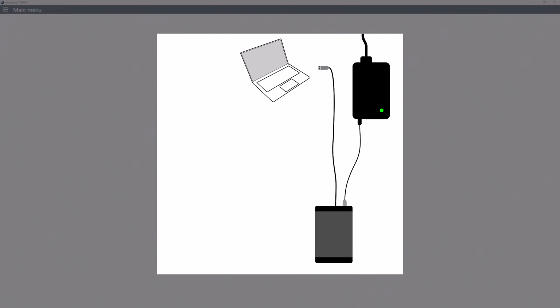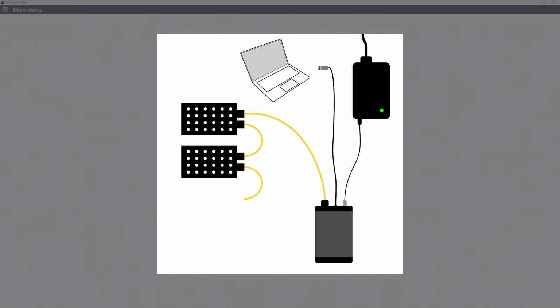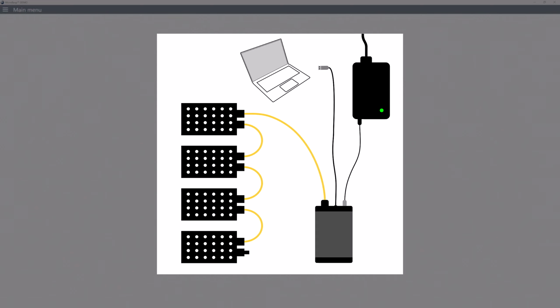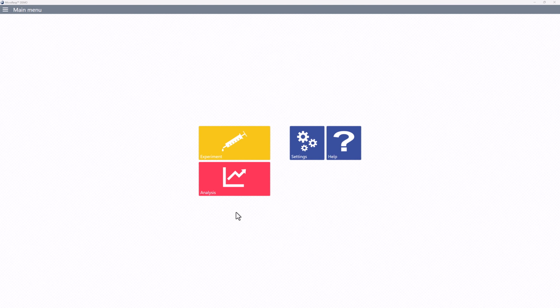Now connect the microplate reader power supply to the splitter, and connect the splitter to your PC via the USB cable. Connect the reader to the splitter. If you have any additional readers, simply daisy chain these to the first reader using the short yellow reader cables. Now connect the power supply to a grounded wall outlet. The microplate reader is now ready to be used in MicroResp.